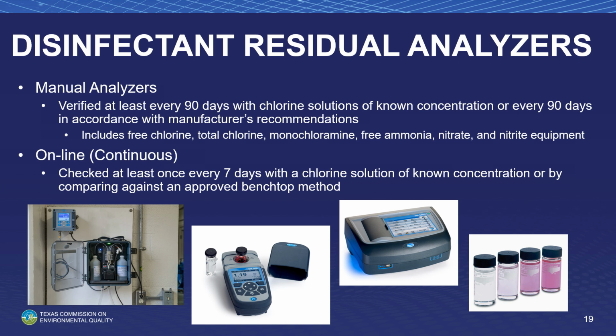Disinfectant residual analyzers, the manual analyzers, so like a DR900 or a DR300, those need to be verified at least once every 90 days with chlorine solutions of known concentrations. Also, a lot of surface water plants will use a total chlorine residual, so you also need to make sure that what you're using to verify how well you are getting a total residual versus a monoresidual, you'll need to verify the accuracy of that as well.